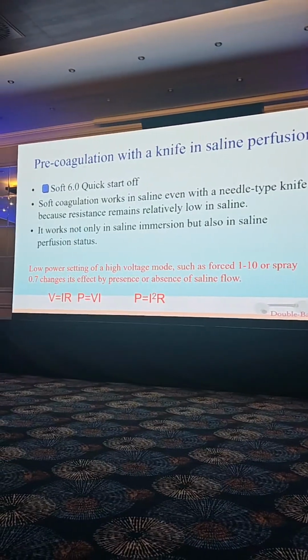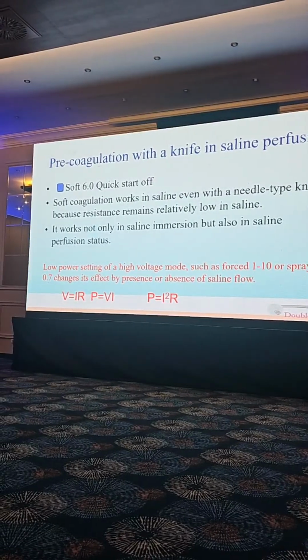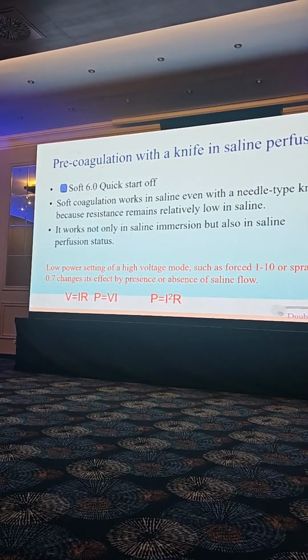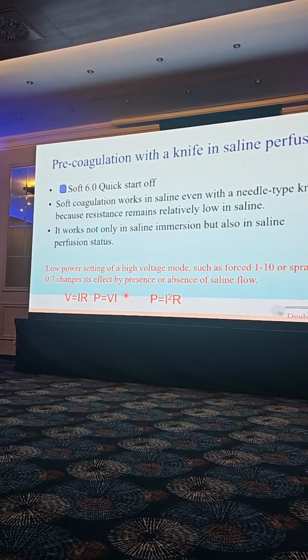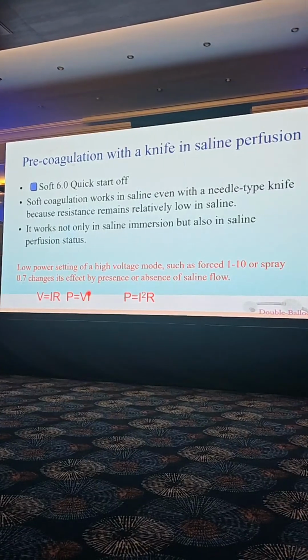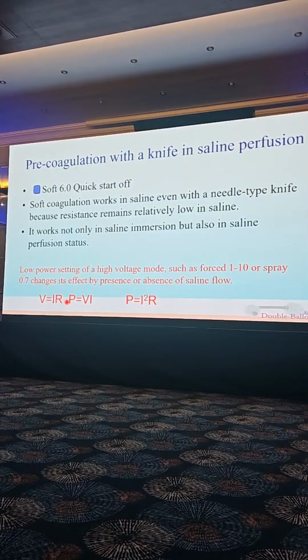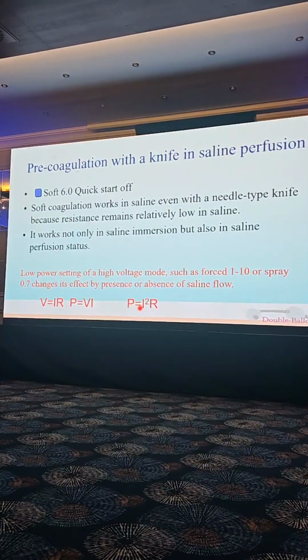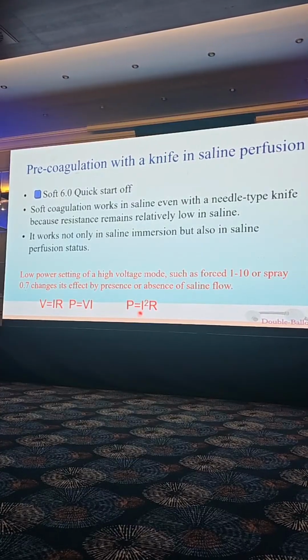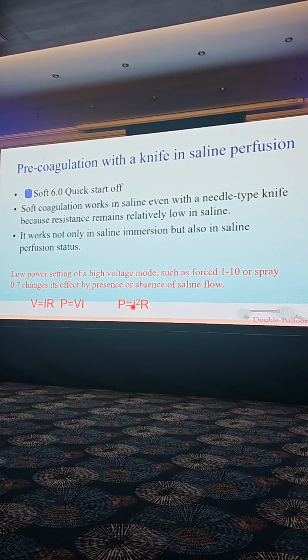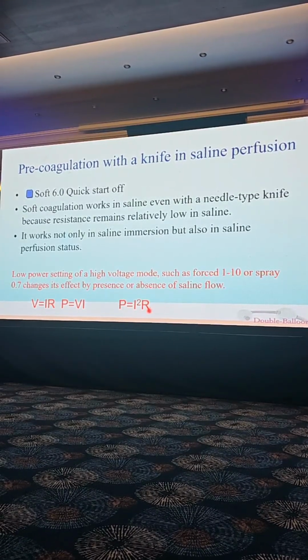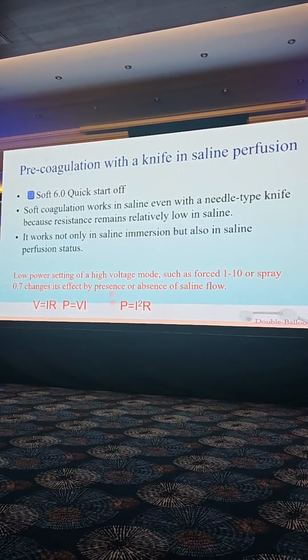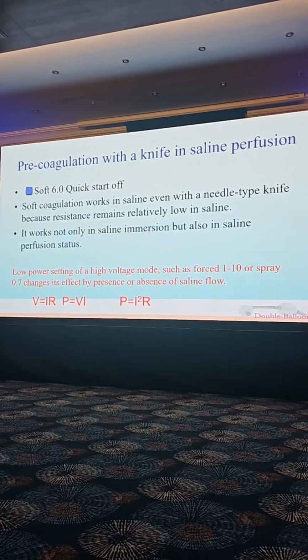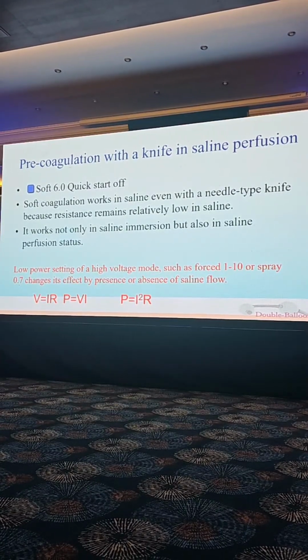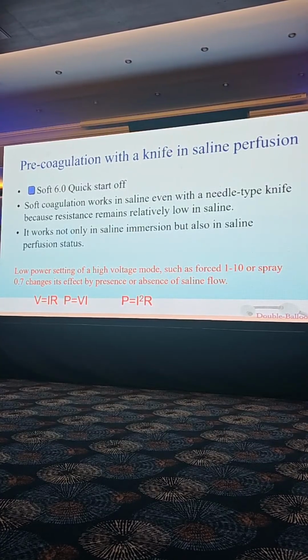But low power setting of high voltage mode, such as spray 0.7, doesn't work very well in saline immersion because the resistance is too low. So the power is voltage times current, and voltage is current times resistance. That means power is the square of current times resistance. So if the current is limited, and the resistance doesn't go up, then it doesn't generate power. So in the saline, the resistance is too low, and there is a flow, so it doesn't work in the saline very well.